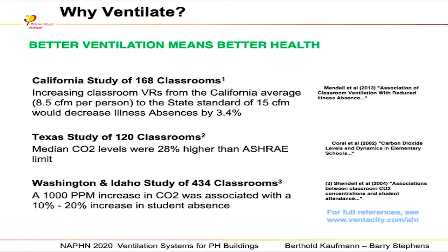Better ventilation means better health, and this is something that's really been rising, especially here in North America. These are some studies on the screen that have been done. California did a study, and they determined that illness absences decreased by 3.4% by increasing from 8.5 CFM per person to 15 CFM per person. For California schools, that translates into not only better health for the students in the school, but by not having as much absenteeism, they actually get more money from the state.